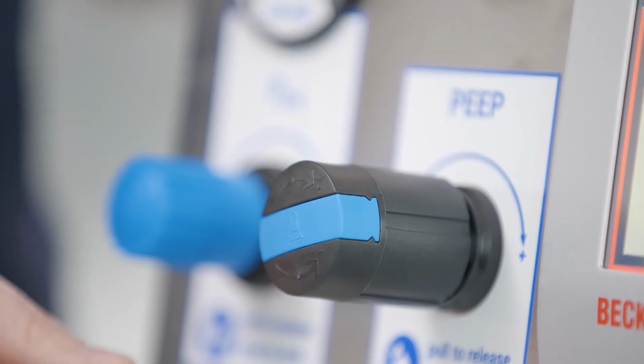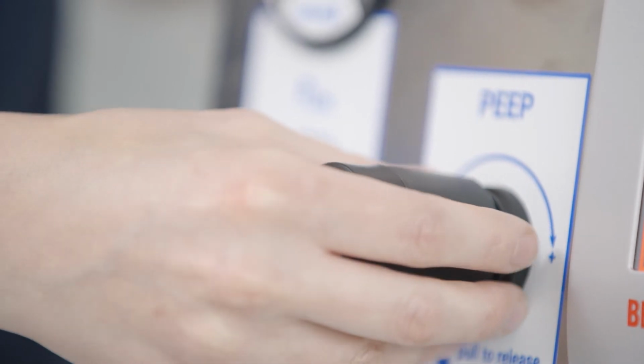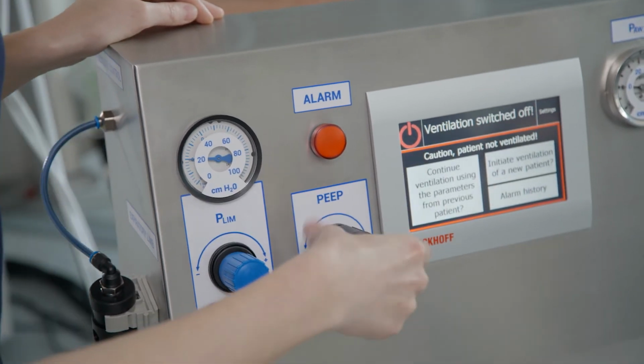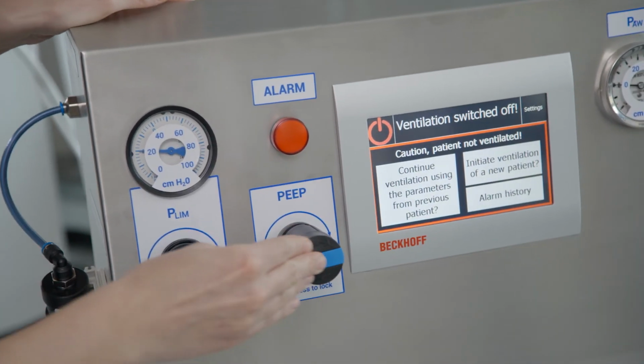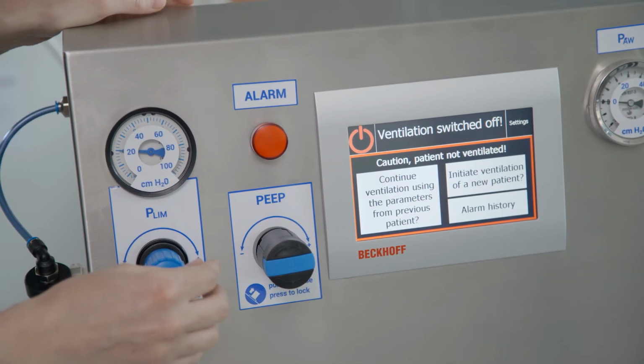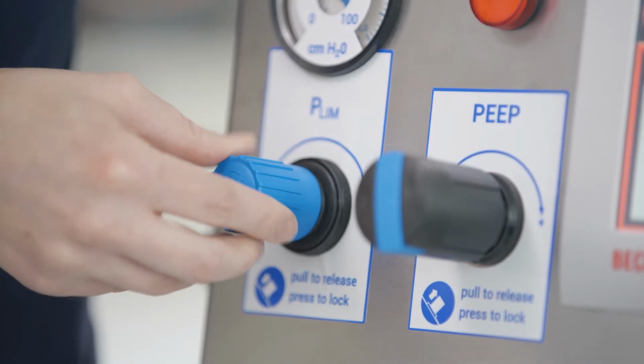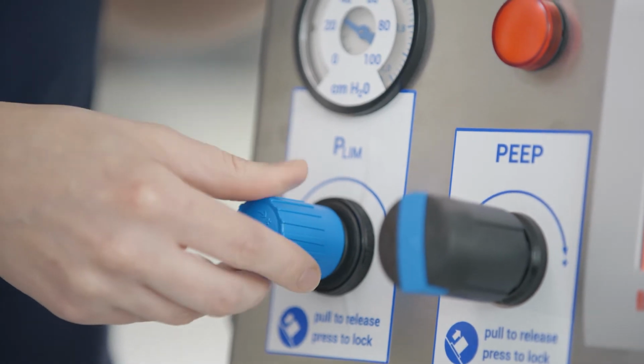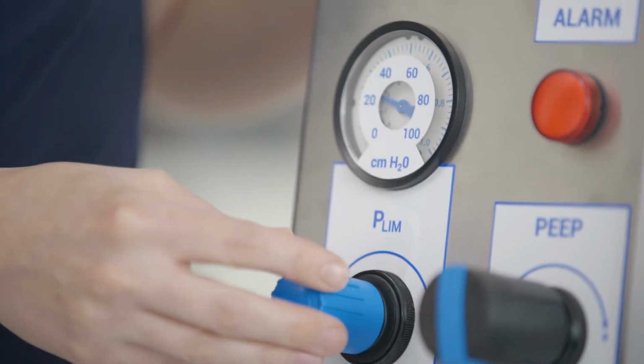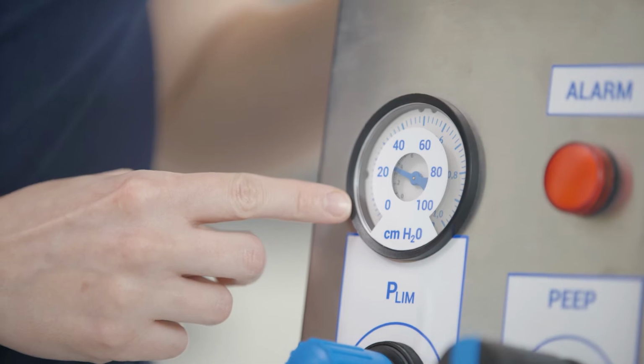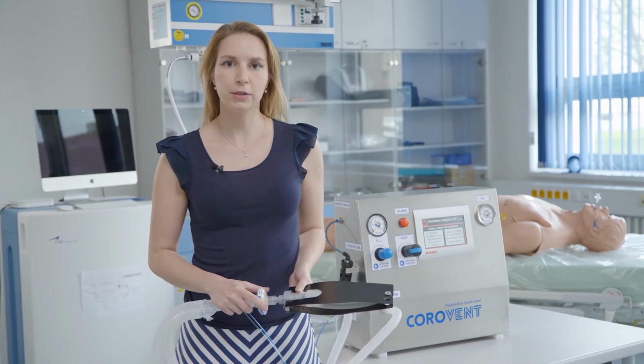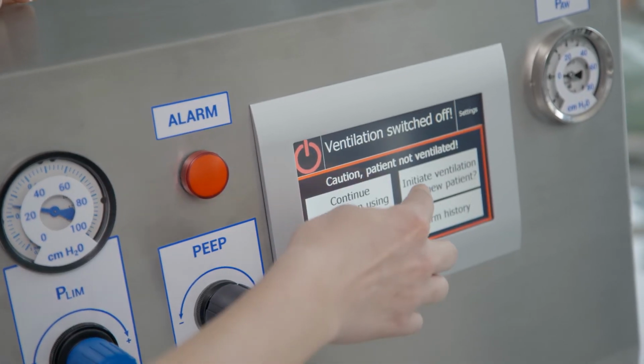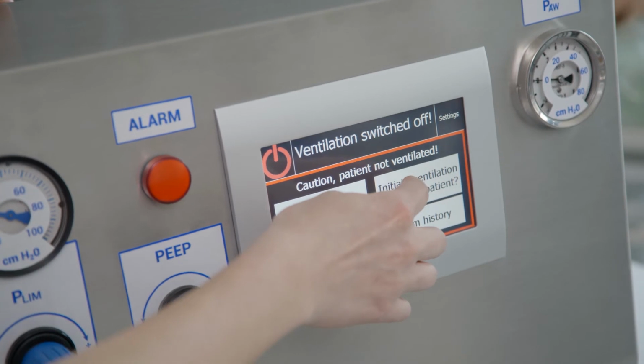Before the ventilation is started, we recommend to set the PEEP to 0 centimeters of water by rotating the knob anti-clockwise. Before we start the ventilation, we recommend to start with PLIM set to 25 centimeters of water. We recommend to set the ventilation parameters on an artificial lung first and then adjust it for an individual patient. And now we can start the ventilation of the new patient.